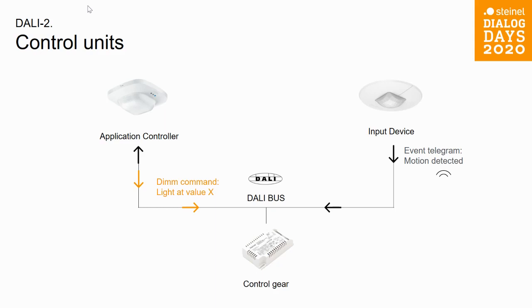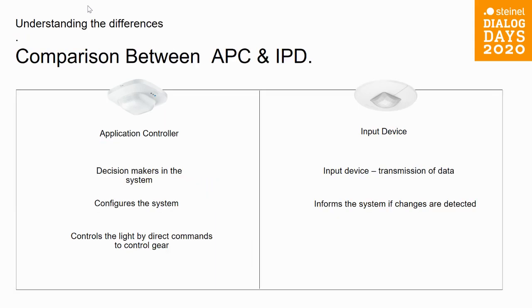An input device is sending an event telegram, so in this case motion has been detected. This is sending the message straight back to either the application controller or a higher end level BMS communication system, ultimately speaking back towards the control gear. When we take a look at the comparison between the application controllers and input devices, the application controller is the decision maker in the system. It configures the system and controls the light by direct commands to the control gear. The input device works purely as a transmission of data and informs the system if changes have been made based on the brightness value or movement, for example.